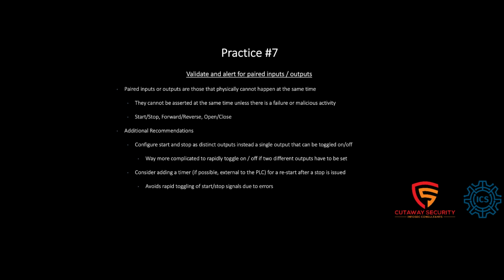Most of these have historically been done for reliability or maintenance purposes. For example, with the limit switches on a valve, if both of them show on, most PLC programs will alert you, because the process engineer or controls engineer has configured that as an alarm to say something is wrong. Not necessarily with security in mind, but for maintenance purposes, because then you can go look at the limit switch to see which one is faulty.